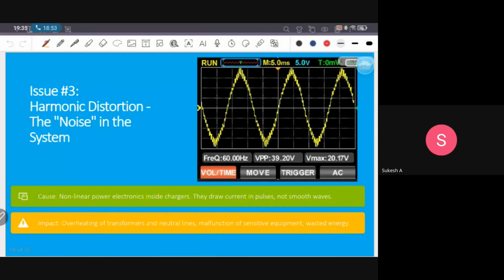And another main concern is harmonics. Harmonics are not transients. Harmonics may be there for many cycles, or minutes, or hours, because our battery is DC. We need DC power. We are rectifying the AC power to DC, and we are using it. The diode bridge rectifier input current THD is around 44% if filters are not used. And even if we are getting pure DC at the DC side, we have to bear a 44% THD in the input current of the rectifier.